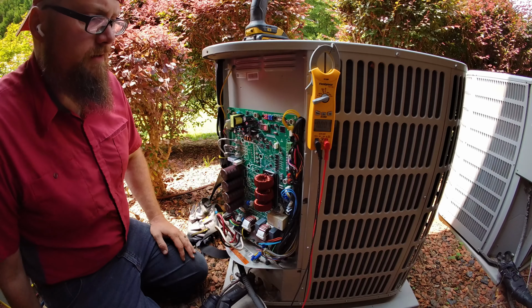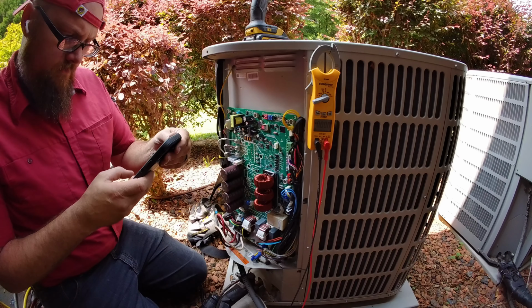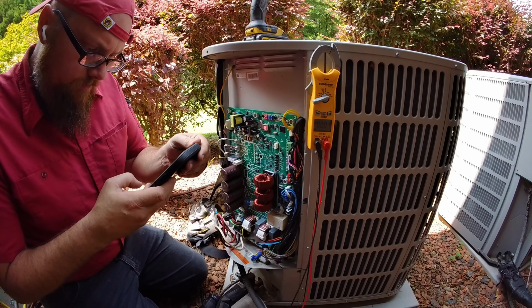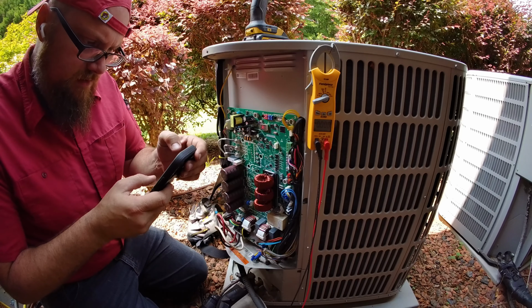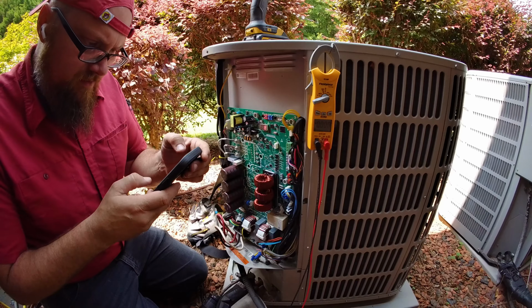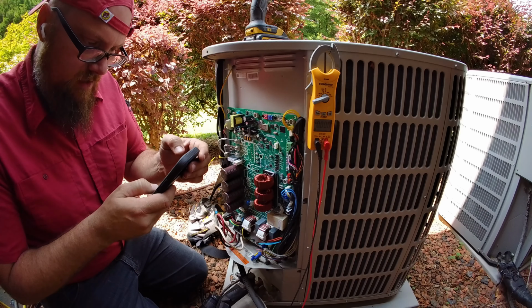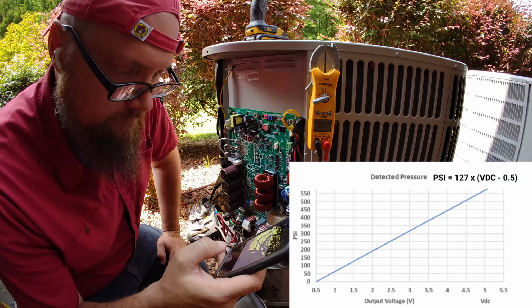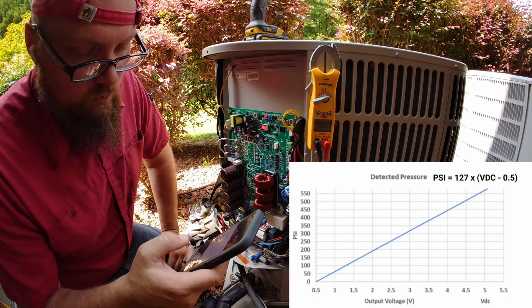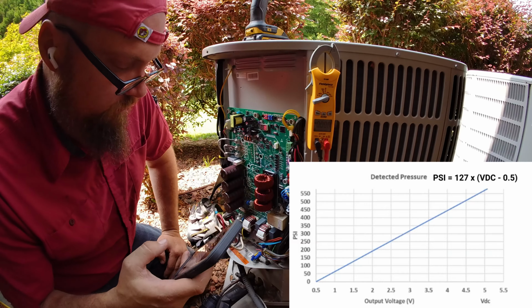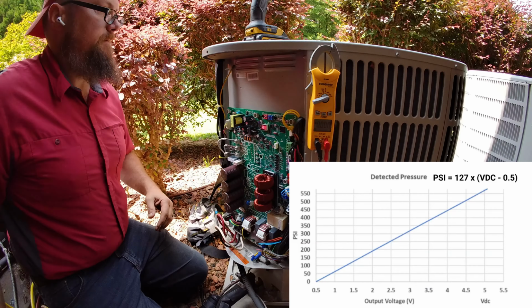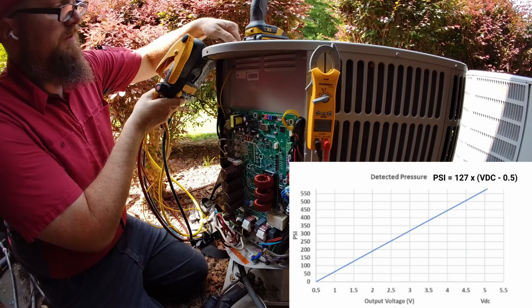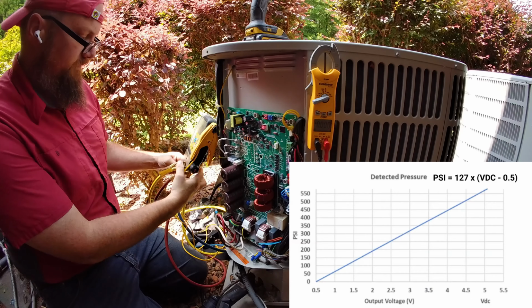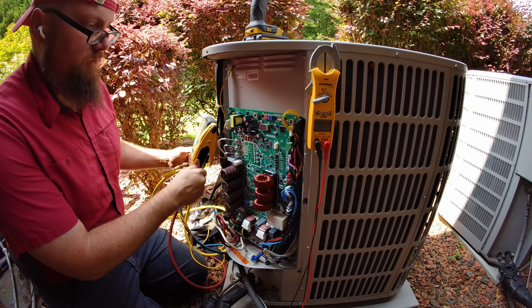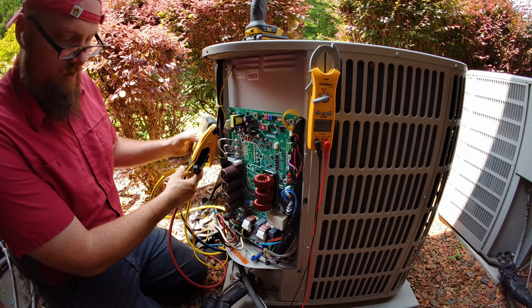And I believe, if I can find my phone here, I'll look this up real quick, because I'm fairly sure if we see anything that low, that is an indication that we have a bad transducer. So yes, according to our chart, 0.5 volts would show us that we were essentially at zero pressure. So we'll check our pressure, but honestly, anything below that 0.5 volts would tell us we have a problem with our transducer, because it should never be able to fall that low.